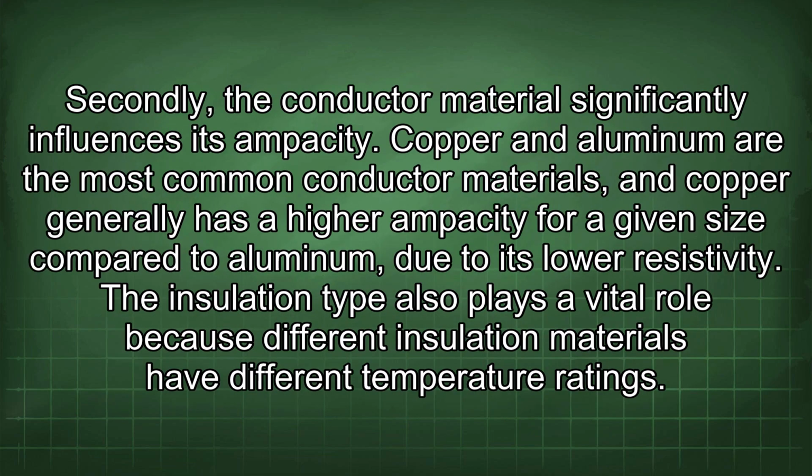Secondly, the conductor material significantly influences its ampacity. Copper and aluminum are the most common conductor materials, and copper generally has a higher ampacity for a given size compared to aluminum, due to its lower resistivity.